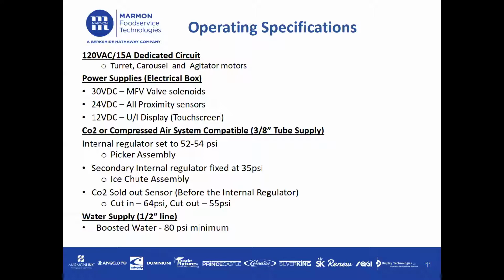There are 3 individual power supplies inside the electrical box. Our first one is 30 volts DC, which powers up our MFV valve solenoids. We have a 24 volts DC power supply, which powers all of our proximity sensors within the unit. And then we have a 12 volts DC that powers up our UI display.